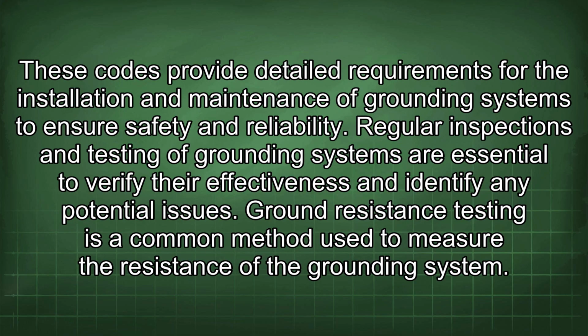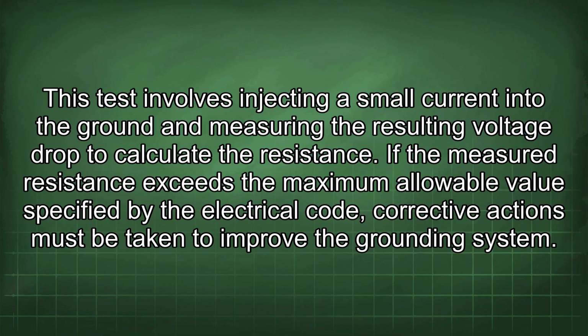Ground resistance testing is a common method used to measure the resistance of the grounding system. This test involves injecting a small current into the ground and measuring the resulting voltage drop to calculate the resistance. If the measured resistance exceeds the maximum allowable value specified by the electrical code, corrective actions must be taken to improve the grounding system.